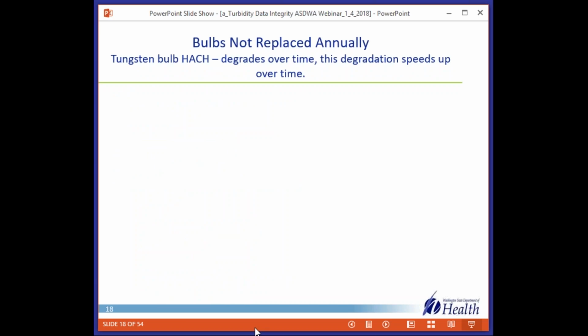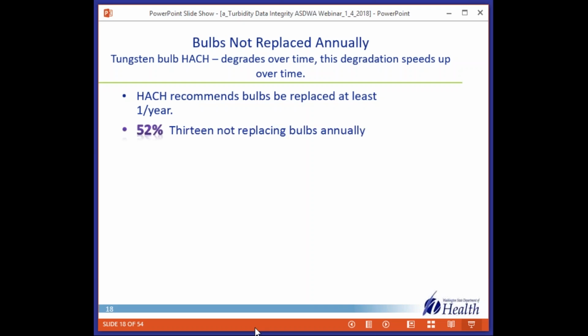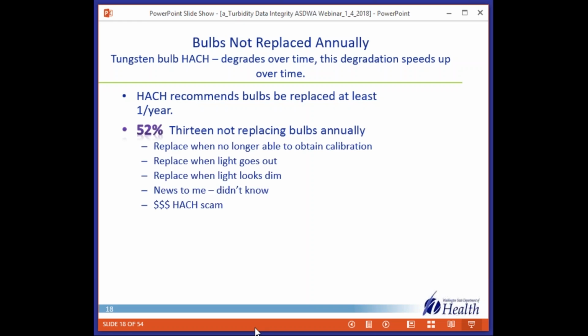Turning to the bulbs on the turbidimeters, the tungsten bulb in the HACH unit degrades over time, and this degradation speeds up over time. So HACH recommends that bulbs be replaced at least once a year. I think of this as akin to replacing smoke detectors annually. 52% of the systems, the 13 systems, were not replacing bulbs annually. And there were different practices in play and different reasons at play for not replacing them annually.